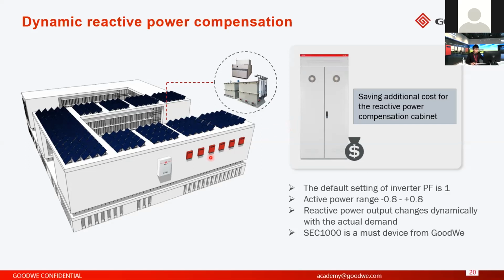So in this case, some customers want the inverter to output not only the active power, but also the reactive power. So that's why we have this function for the customers. As you know, the default power factor setting of the inverter is 1, so the inverter only outputs active power, no reactive power. But if the customer wants to get reactive power from the inverter, we also have a solution. The customer just needs to buy the control box, named SEC 1000. This box will control the inverter to output active power and also reactive power according to the load's consumption. So that's dynamic reactive power compensation, not static reactive power compensation.